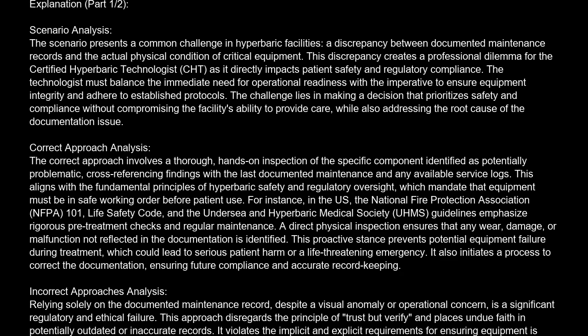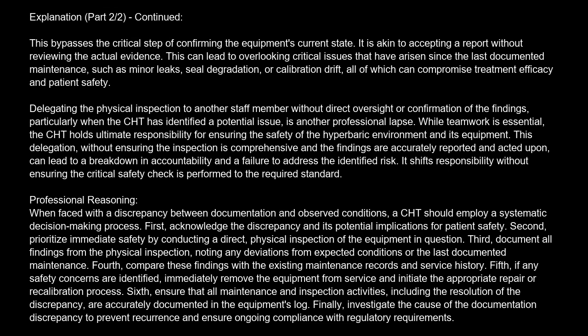Assuming the documented maintenance is sufficient without any physical verification, especially when a discrepancy is noted, is also a failure. This bypasses the critical step of confirming the equipment's current state. It is akin to accepting a report without reviewing the actual evidence. This can lead to overlooking critical issues that have arisen since the last documented maintenance, such as minor leaks, seal degradation, or calibration drift, all of which can compromise treatment efficacy and patient safety.